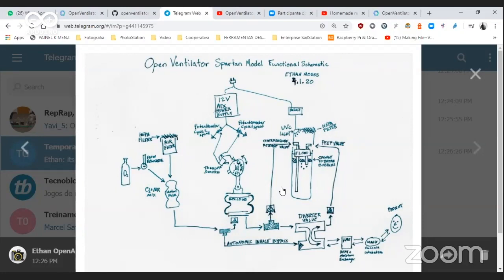That's why, for example, in the Spartan model, we are using a simple end switch and a relay to have 2 speeds to adjust, or maybe 3 or 4 with some resistors, and so we can manually jack in a plug and jack out from one plug to another to have this kind of resolution between inspiration and expiration timing. Also for the frequency, we have to put a potentiometer to increase the voltage on the motor.